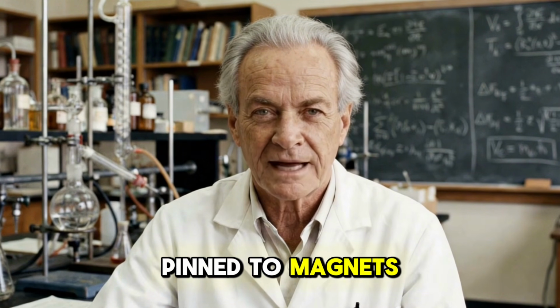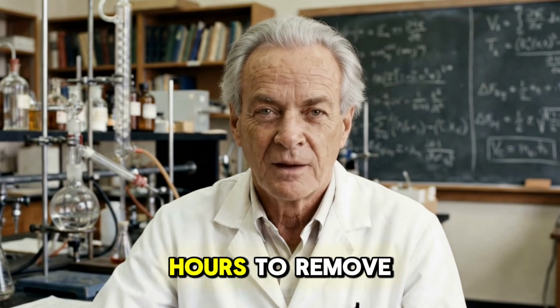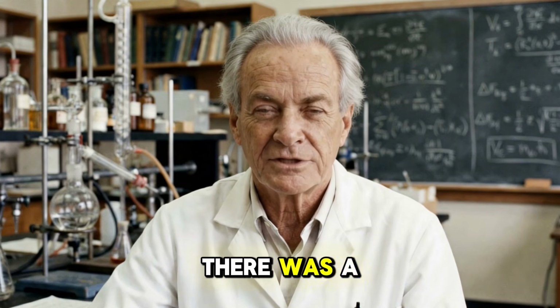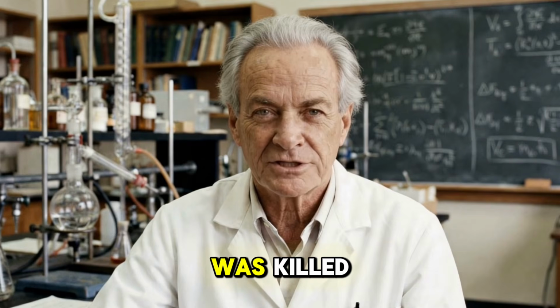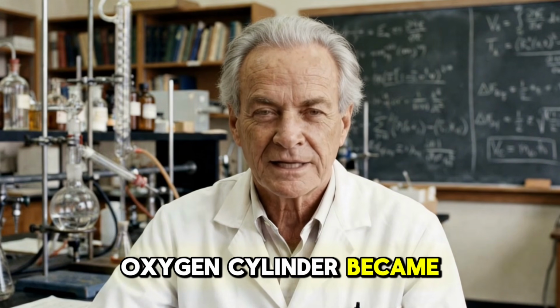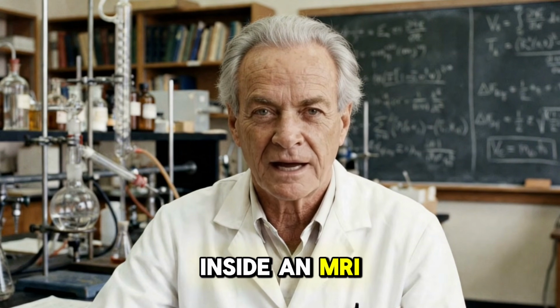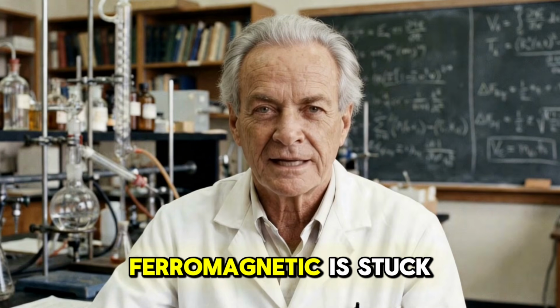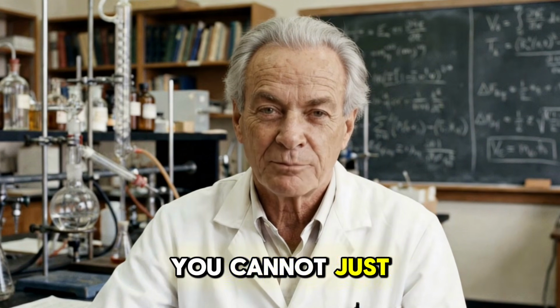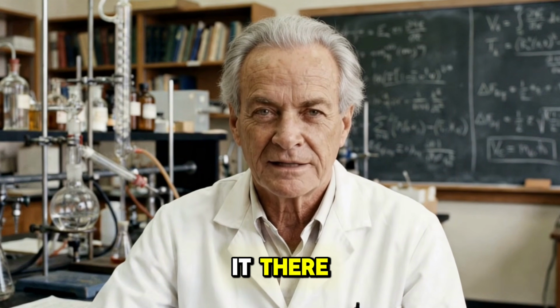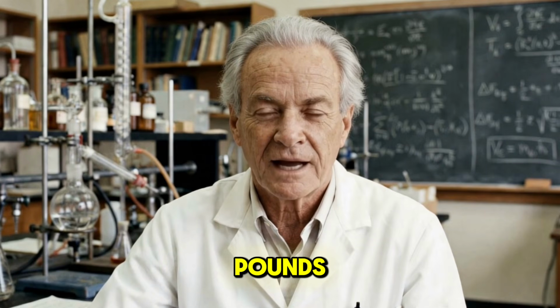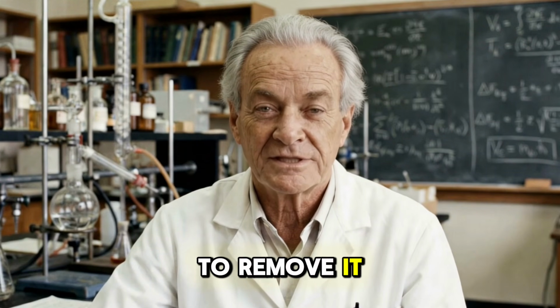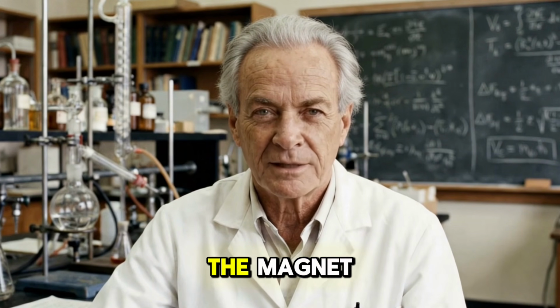Wheelchairs have been pinned to magnets with such force that it took hours to remove them safely. There was a tragic case where a child was killed when a ferrous oxygen cylinder became a missile inside an MRI room. And once something ferromagnetic is stuck to the magnet, you cannot just pull it off. The force holding it there can be hundreds or thousands of pounds. The only way to remove it safely in many cases is to quench the magnet.